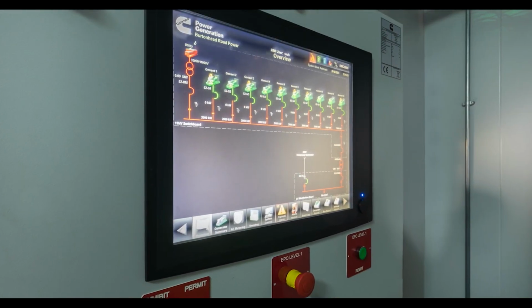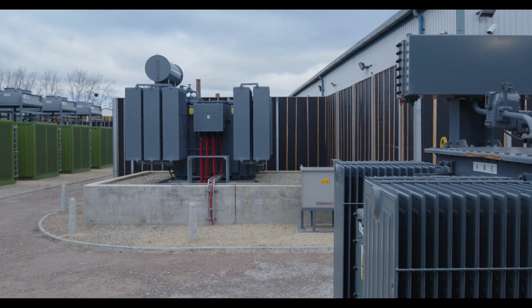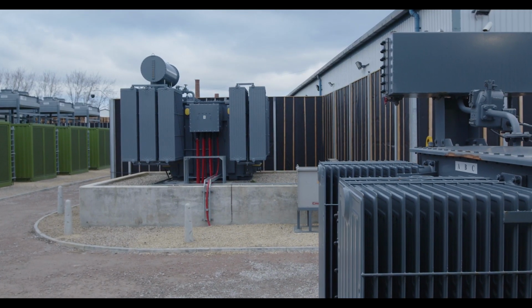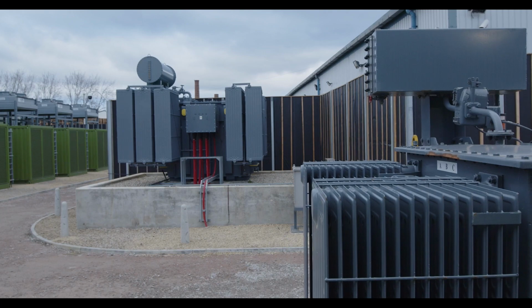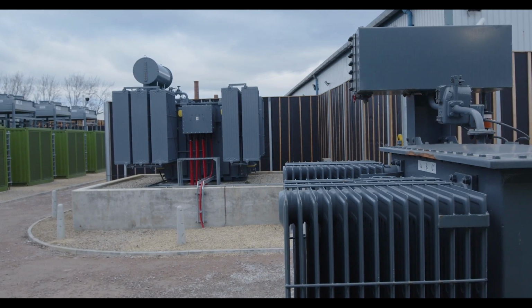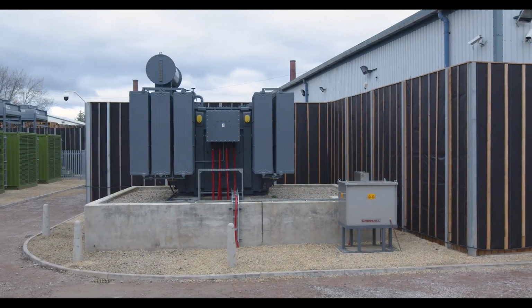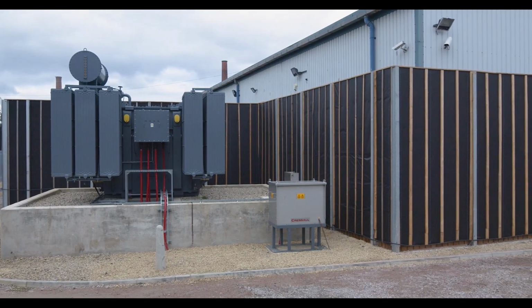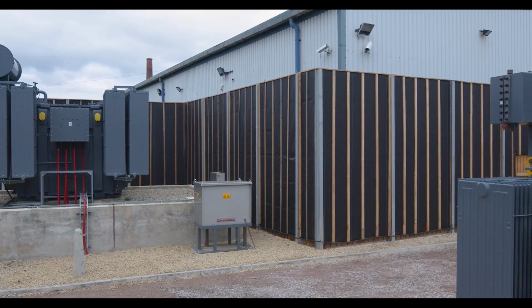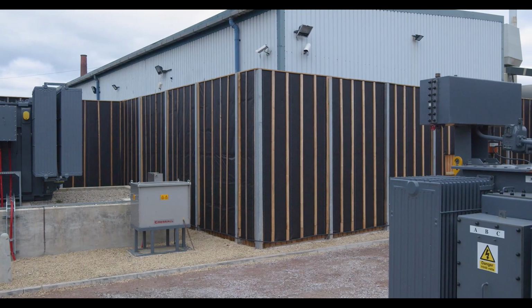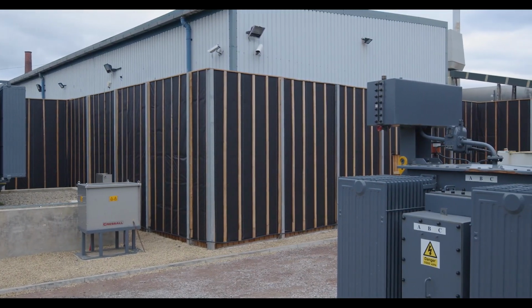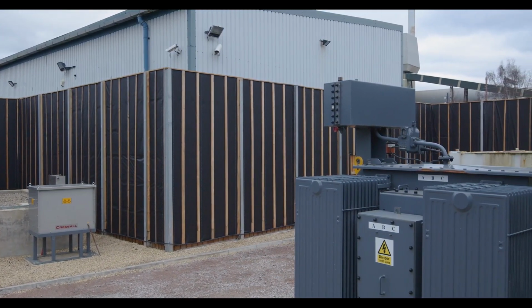From the high voltage switch room, the electricity is passed through, still at 11,000 volts, under the road to the primary grid transformer. This primary grid transformer takes electricity in on the low voltage side at 11,000 volts, as you can see with the red cables. It then steps the voltage up to 33,000 volts to match the voltage of the Scottish Power grid network.